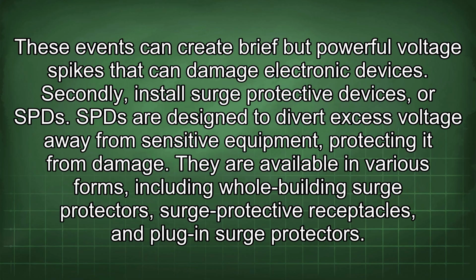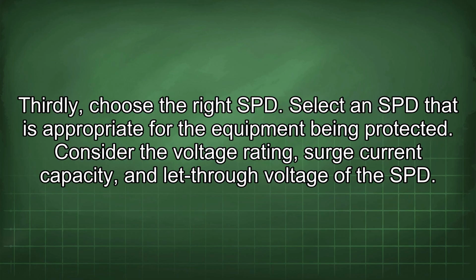Secondly, install surge protective devices, or SPDs. SPDs are designed to divert excess voltage away from sensitive equipment, protecting it from damage. They are available in various forms, including whole building surge protectors, surge protective receptacles, and plug-in surge protectors. Thirdly, choose the right SPD. Select an SPD that is appropriate for the equipment being protected. Consider the voltage rating, surge current capacity, and let-through voltage of the SPD.